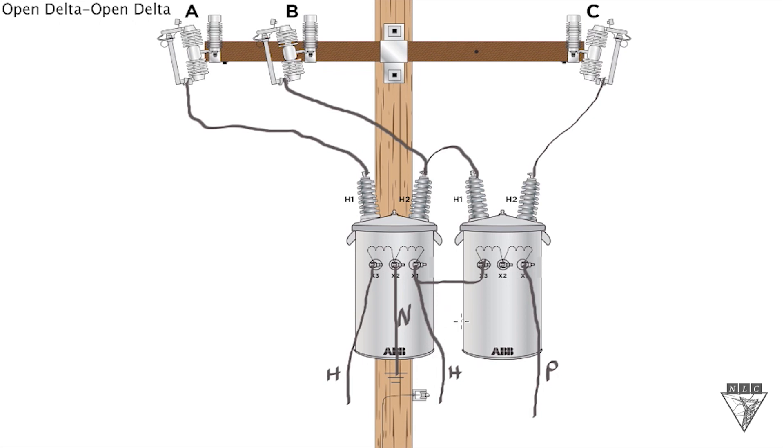But let's say the customer also needs some three phase power, it's just a smaller three phase power. That's why you've got this open bank with this other transformer. So now you have all three, you got two hot legs and the power leg to utilize for your three phase power.